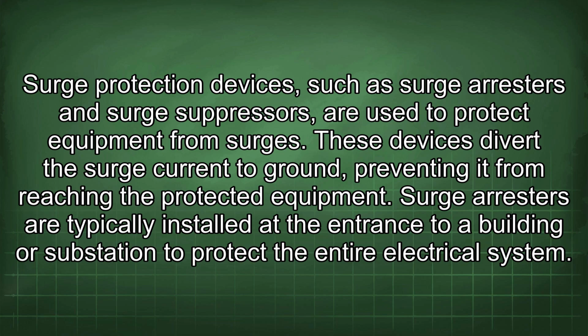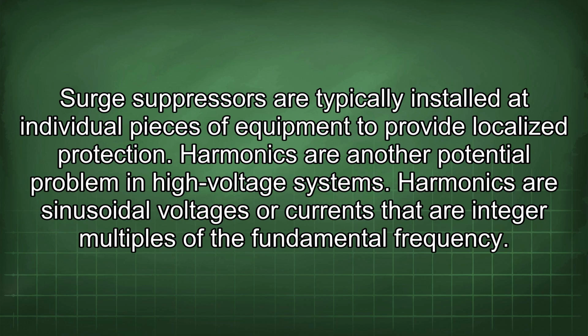These devices divert the surge current to ground, preventing it from reaching the protected equipment. Surge arresters are typically installed at the entrance to a building or substation to protect the entire electrical system. Surge suppressors are typically installed at individual pieces of equipment to provide localized protection.